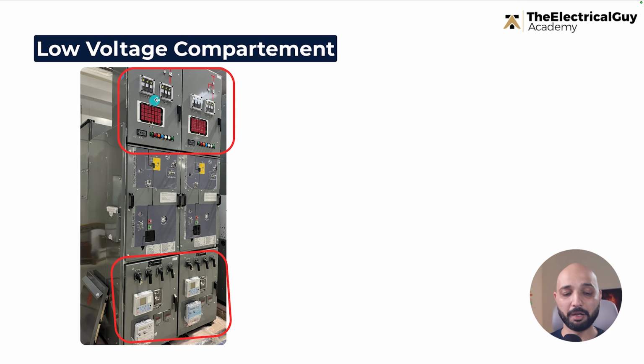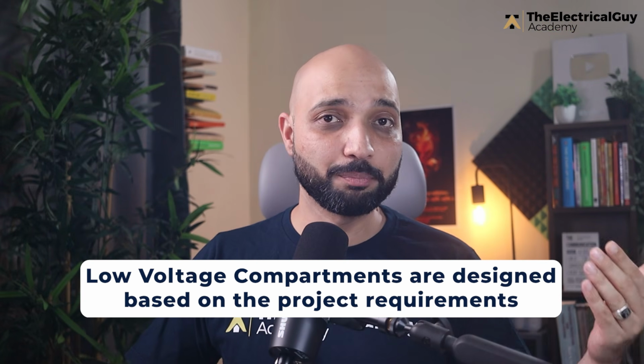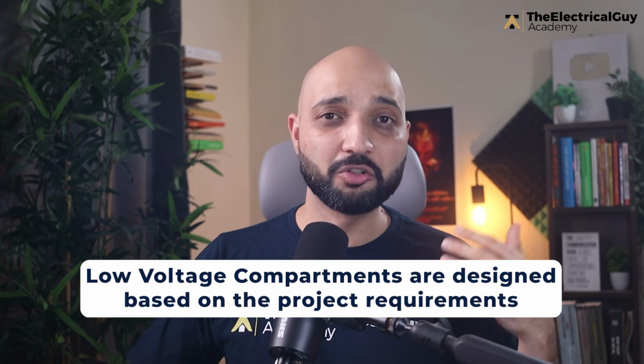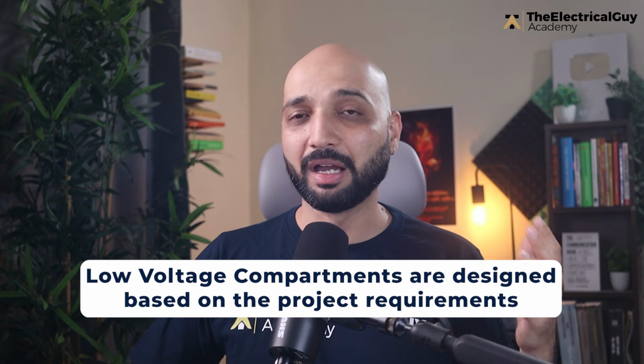Now I want you to remember one thing: there is no standard design when it comes to the low voltage box or low voltage compartment. It will change based on the project's requirement. It will change based on the manufacturer's design, and it will for sure change based on what kind of protection and what kind of indications you want.